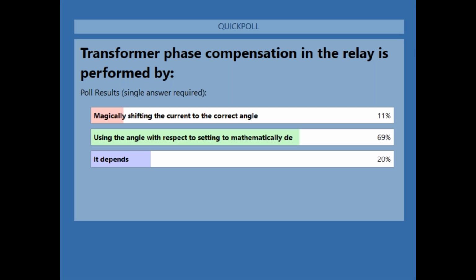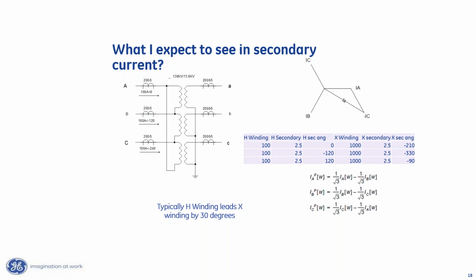If you want to live in the magical universe reality, then you can believe that it just magically shifts those currents based on the angle with respect to setting. If you want to live in a mathematical universe, or if you happen to be a guy that tests the relay, you need to live in the actual universe, which is how this is actually done. What we actually do inside the relay algorithm, based on that angle with respect to setting, is we calculate a compensation matrix. That compensation matrix takes a combination of the currents that are wired to the relay and uses that combination of the currents to compensate.